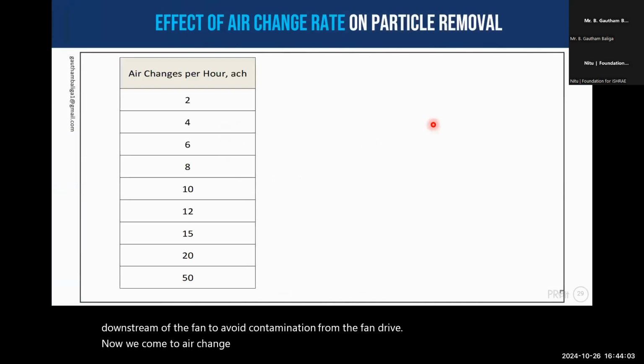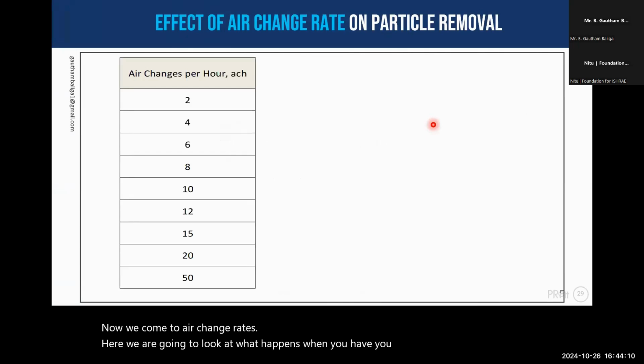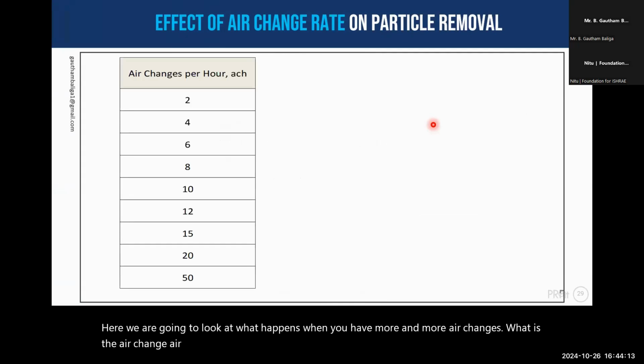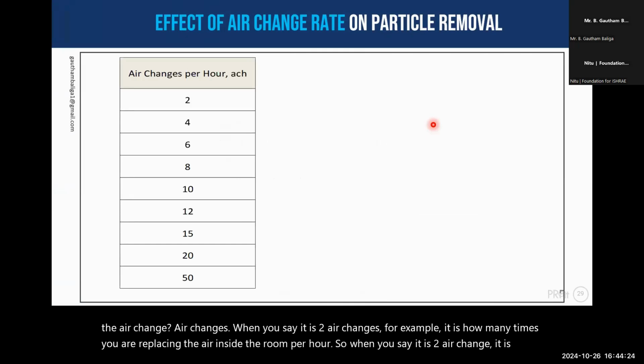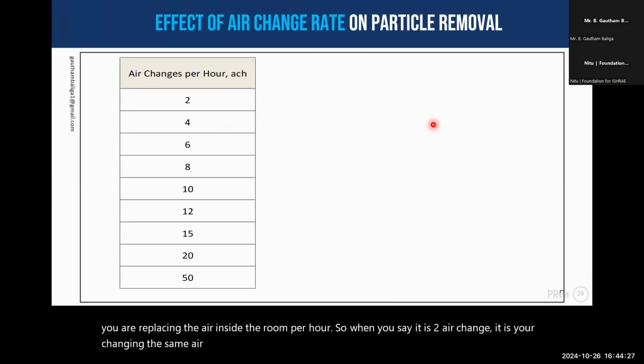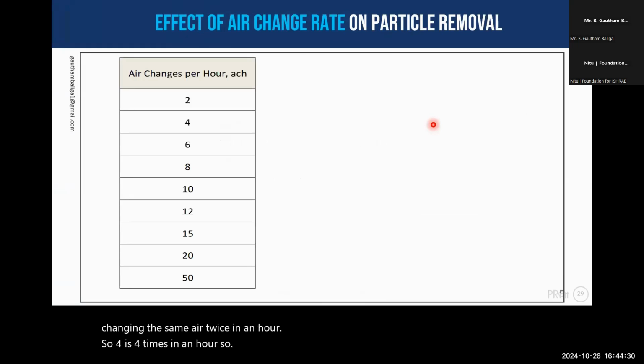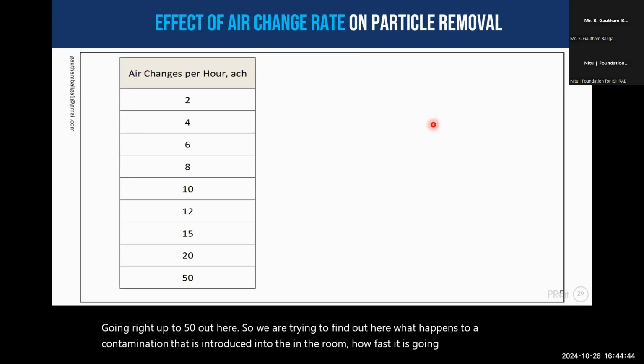Now we come to air change rates. Here we are going to look at what happens when you have more and more air changes. What is an air change? When you say it is two air changes, for example, it is how many times you are replacing the air inside the room per hour. So when you say it is two air changes, you're changing the same air twice in an hour. So four is four times in an hour. So going right up to 50 out here. So we are trying to find out here what happens to a contamination that is introduced into the room, how fast it is going to dilute to 1% of its original concentration.